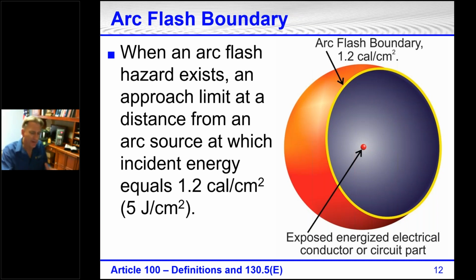But if I have a piece of equipment open, and the arc flash boundary was calculated at being 3 feet, the further away I go, if I go 4, 5, 6, 7 feet, do you think the arc flash or the incident energy goes up, or do you think it goes down the further away I get? Exactly, it does go down. So if we say the arc flash is 5 calories at 3 feet, you keep going back further.